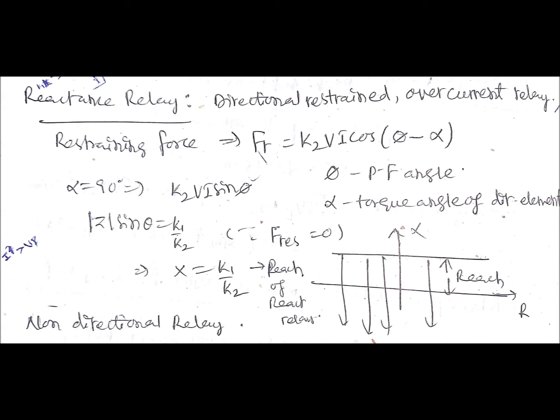In case of distance relays we also have the reactance relay — all are in ohm values, that is impedance values. Reactance is a part of impedance with only purely imaginary quantities and no resistance. This is a directional-restrained overcurrent relay, meaning a directional element gives the restraining force and current gives the operating force. The restraining force is FR = k2·V·I·cos(φ − α), where φ is the power factor angle of the load and α is the torque angle of the directional element.